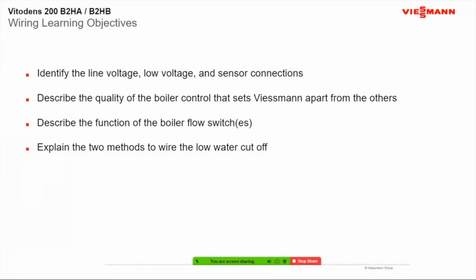So that was just a little quick presentation of wiring and low voltage where the sensors go. Just remember things where you can switch pumps from primary to secondary for your domestic, things like that, as well as your flow switches. Remember, they have flow switches and flow sensors. If you're cleaning the flow sensors, you don't want to poke it or anything like that because it is a sensor. Just wipe it off.